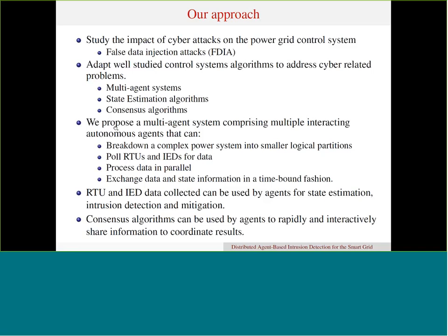Okay, so as I was saying, we're proposing the use of multi-agent systems for detecting intrusions in the power grid. A multi-agent system would consist of intelligent agents that interact autonomously and can be equipped with capabilities such as breaking the power grid into logical partitions, having access to RTU and IED data, and processing this data in parallel, exchanging information among themselves in a time-bound manner, and running whatever algorithm they are allowed to run locally where they are. They can even make decisions, like determining if the data they have collected from an RTU or IED has been affected by false data or some other attack, and then share this with their neighbors in order to come up with coordinated results, right?